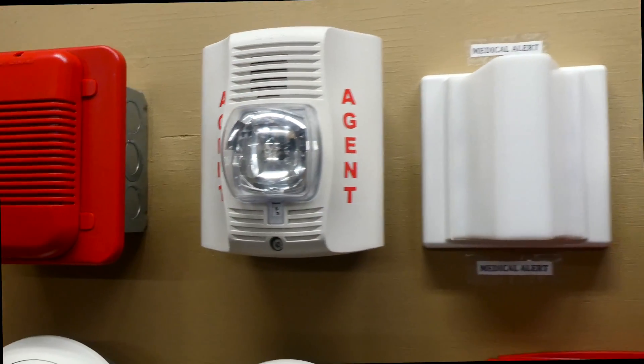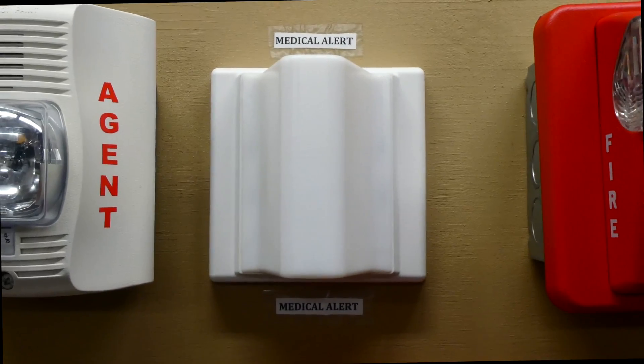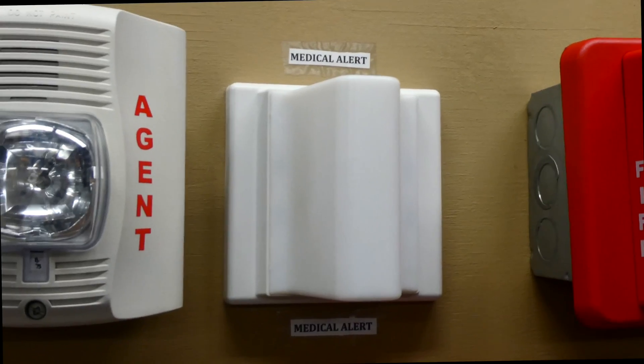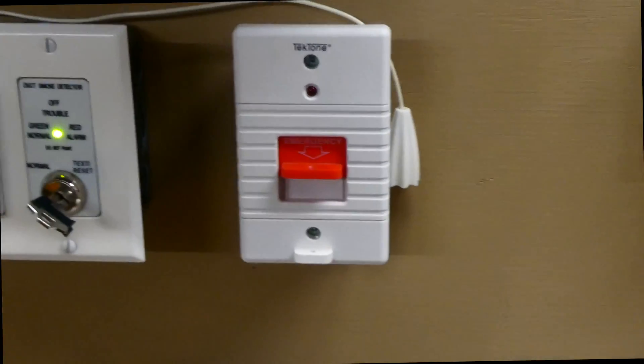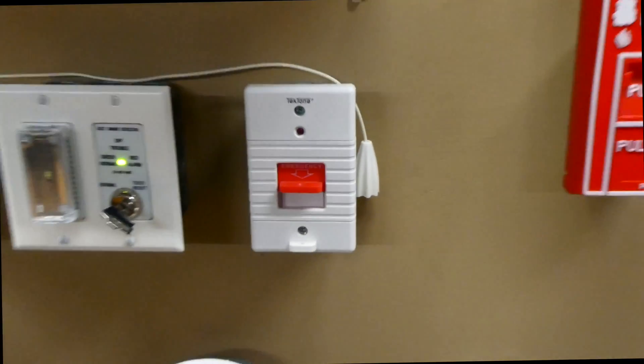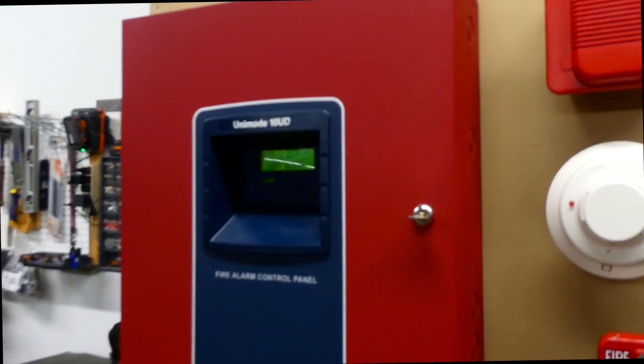To the right of the Agent Spectralert Advance, we have a Tek-Tone corridor light. We're also going to try and test this today. This is just a medical corridor light — you see these all the time in hospitals. Basically, if you activate something like a Tek-Tone pull cord, it will activate the corridor light and set off some alarms. But on this system, only the corridor light is wired up. Fire alarm control panels usually don't run those medical alert systems, but they can sometimes.